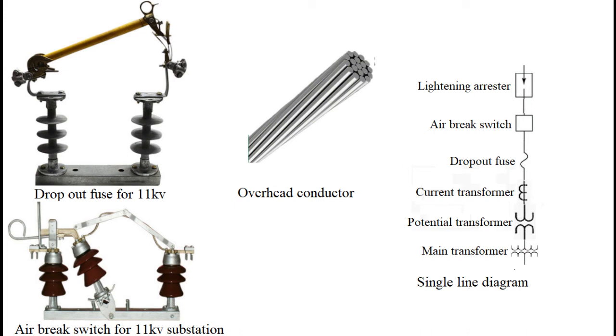An 11 kV by 433 volts substation is, in real sense, simply a distribution transformer that is given with metering CT and PT, air break switch, dropout fuses, and distribution panel on the LT or low tension side. The transformer may be pole mounted or plinth mounted depending upon its size. A transformer with approximately less than 500 kVA rating is placed on poles, and if the transformer is greater than 500 kVA rating, then it is placed on a plinth.